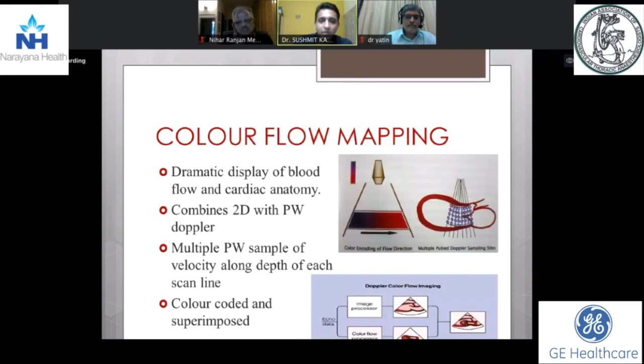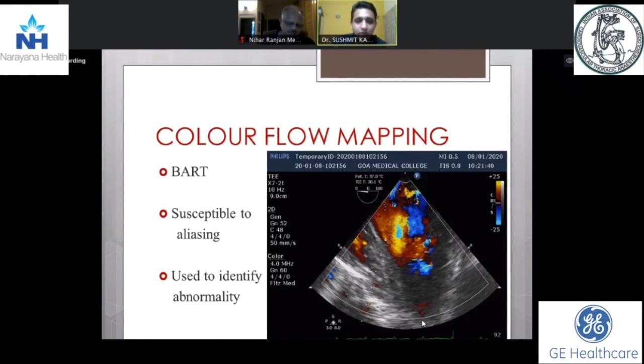Color flow mapping combines 2D and pulsed wave Doppler to give a 2D image which shows us the velocity of blood. Blue color denotes flow away from the transducer and red towards. And since it uses pulsed wave Doppler, it is also susceptible to aliasing. So color flow mapping is basically just used to identify the abnormality, which should be further interrogated using either pulsed wave Doppler or continuous wave Doppler.